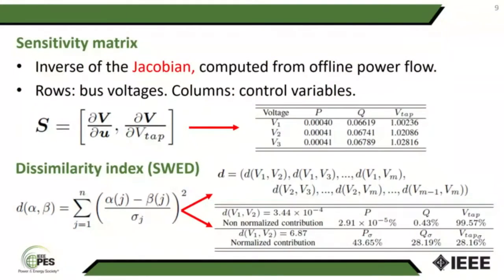The characteristics that we use for each bus are the voltage sensitivities to the control variables. In this sense, we can define a sensitivity matrix with the same number of rows as the number of measured buses and the same number of columns as the control variables. Such sensitivities are approximated using offline power flows of the system. An example of the magnitude of these three numbers is presented on this table over here. Observe how the bus voltages are more sensitive to certain variables than others.